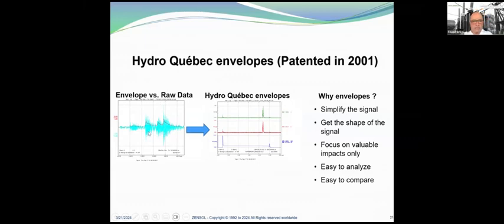Here you can see in blue the raw data, which is the typical vibro-acoustic signal given by an accelerometer. And in red, you can see what we call Hydro-Quebec envelopes, which were patented in 2001 by Hydro-Quebec. And here you can see the current. Here we call this the high frequency envelope, and here the low frequency envelope. So why envelopes? Because it simplifies the signal and gets the shape of the signal. This way we can focus on valuable impacts only. And our target is to have something easy to analyze and easy to compare with a reference.